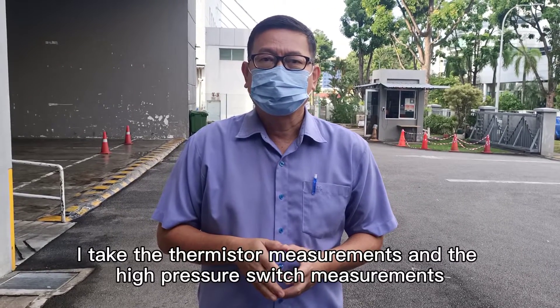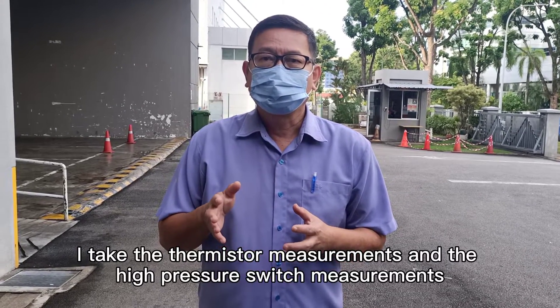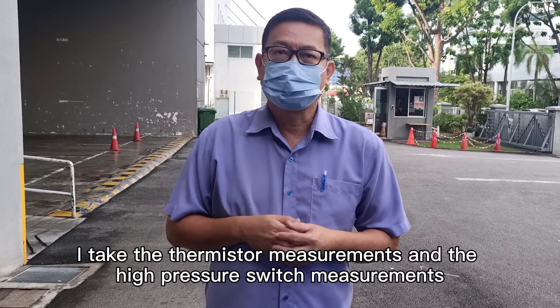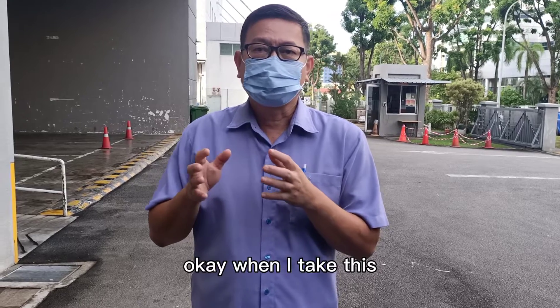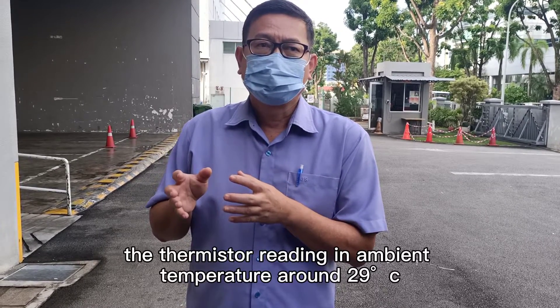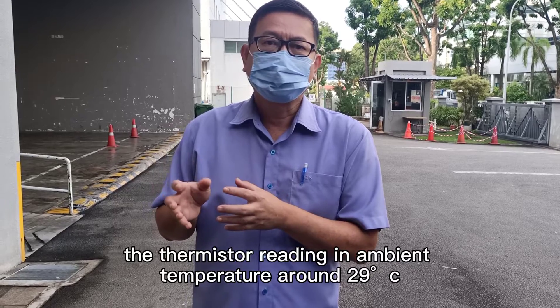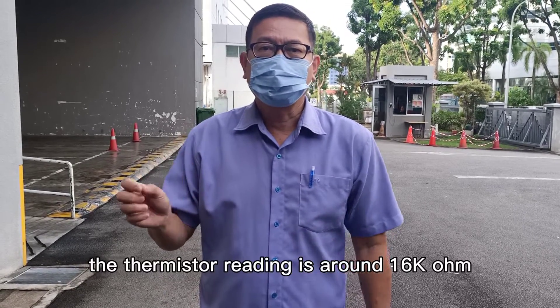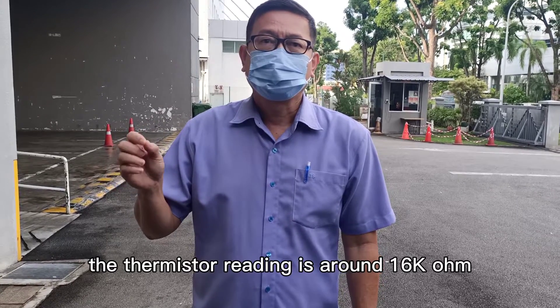In this video, I take the thermistor measurement and the high-pressure switch, low-pressure switch measurement, just as an example. When I take this thermistor reading, the ambient temperature is around 29 degrees, and the thermistor reading is around 16 kilo-ohm.